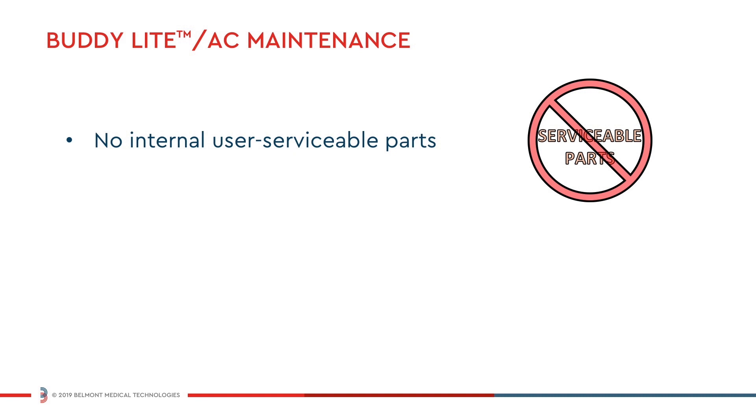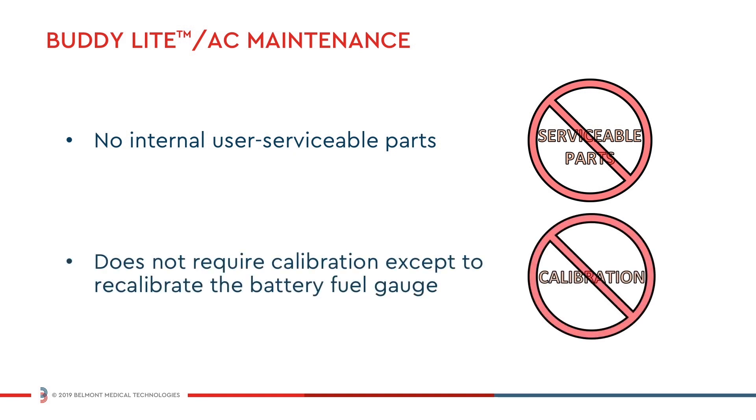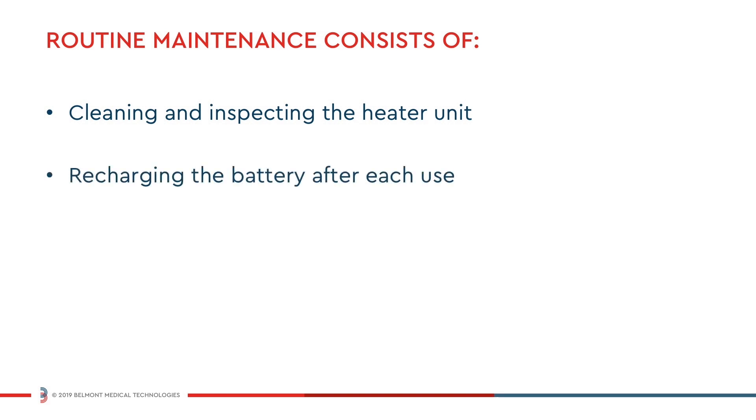The system has no internal, user-serviceable parts and does not require calibration except to recalibrate the battery fuel gauge. Routine maintenance consists of cleaning and inspecting the heater unit, recharging the battery after each use, and recalibrating the battery fuel gauge if required.